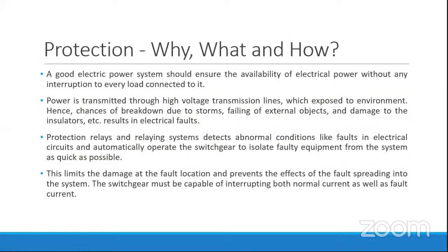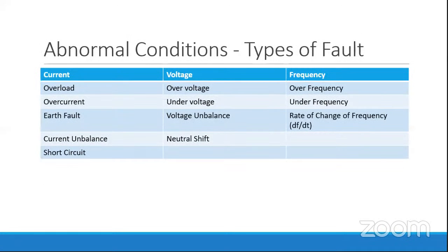So, abnormal conditions or types of faults. The faults can be classified into three types. The fault will be in terms of current, voltage, and frequency. So for current, we can say overload. This overload will be an abnormal condition. It will not be considered a fault. Overcurrent we can also say is an abnormal condition; we cannot say it is a fault. The earth fault is actually a fault. Current unbalance and short circuits, like three phase fault, line to ground fault, double line to ground fault, and double line fault, will be considered short circuit faults.